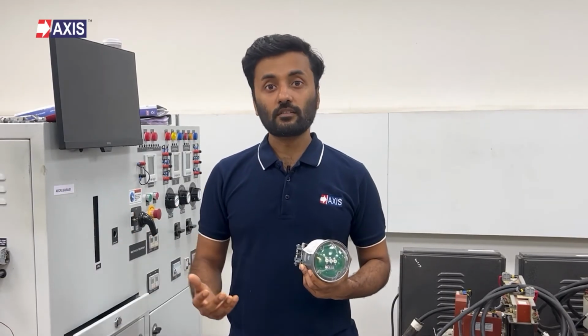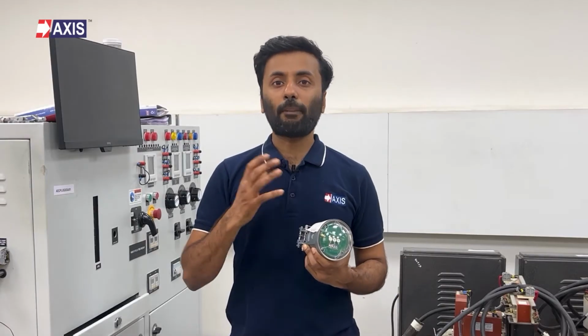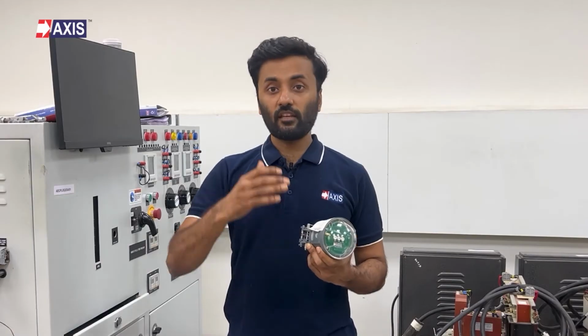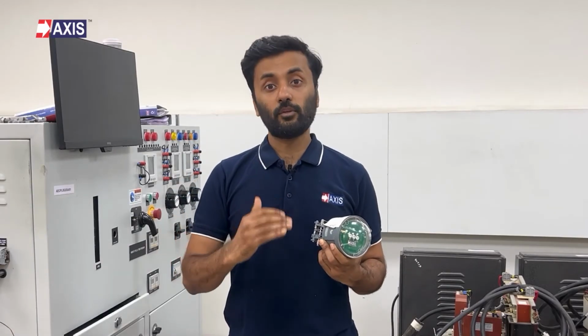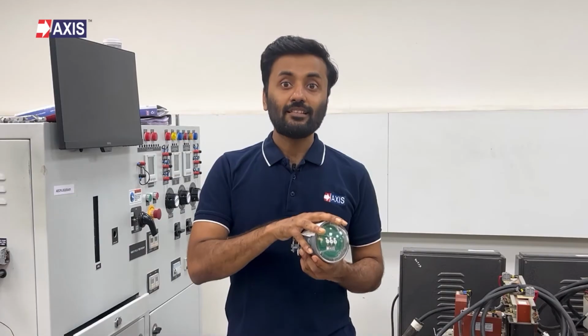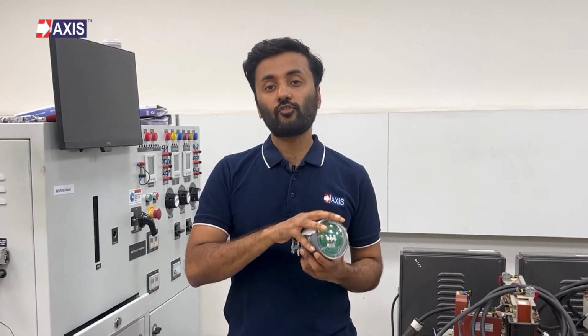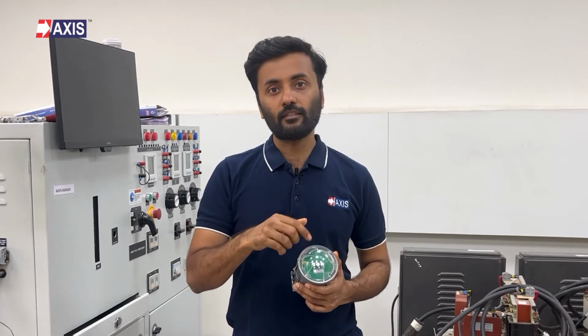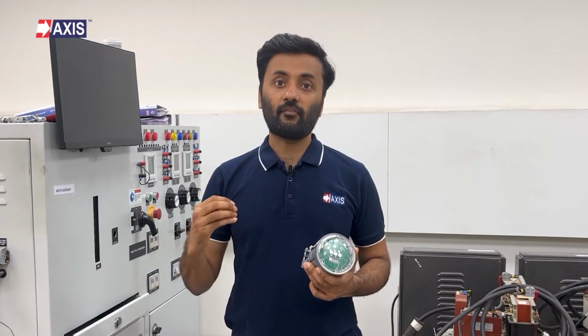When a fault occurs, the conductor's magnetic field spikes due to a surge of high current flowing through the device, which then drops to zero as the circuit breaker trips. The FPI senses this abrupt change and triggers an alert. The fault indicating LED on the FPI starts blinking to indicate the faulty condition at the site when a non-communicable type FPI is used. And when a communicable type FPI is used, a remote signal is sent to the SCADA center in case of a fault.